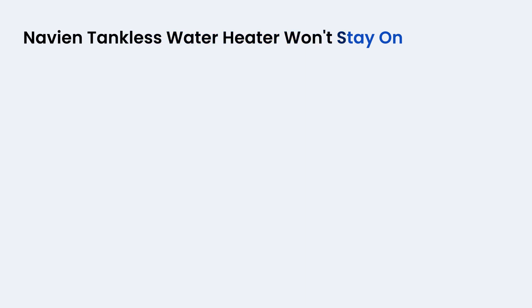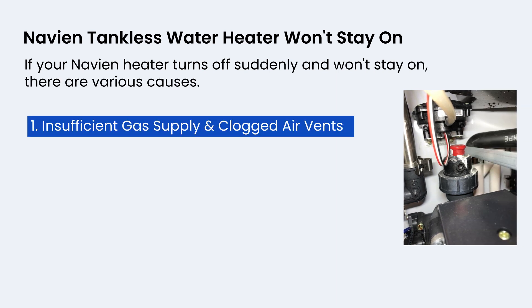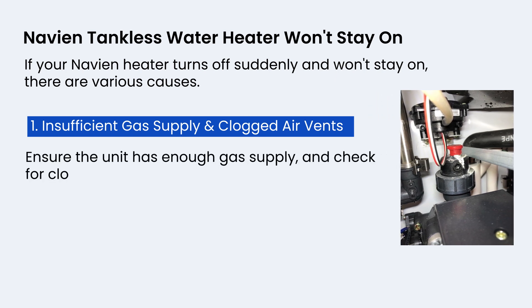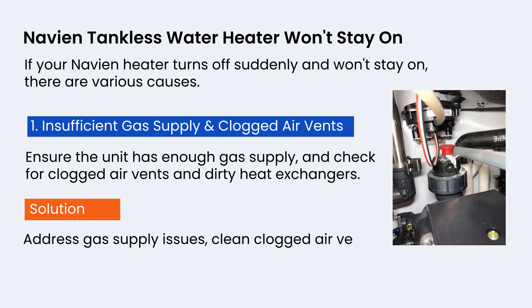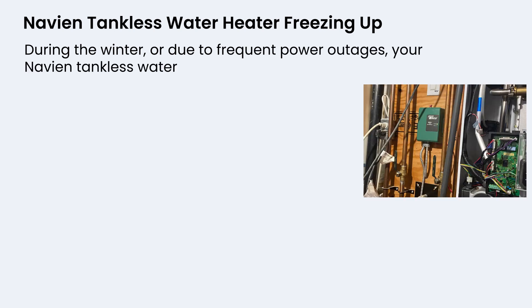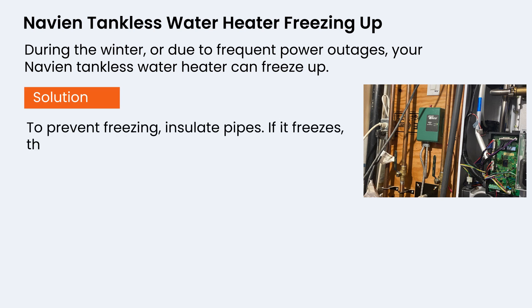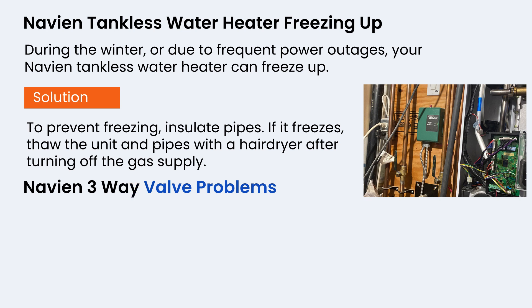If your Navien heater turns off suddenly and won't stay on, ensure the unit has enough gas supply and check for clogged air vents and dirty heat exchangers. Address gas supply issues, clean clogged air vents, and flush the heat exchanger — if unsure, consult a professional. During the winter or due to frequent power outages, your Navien tankless water heater can freeze up. To prevent freezing, insulate the pipes. If it does freeze, thaw the unit and pipes with a hairdryer after turning off the gas supply.